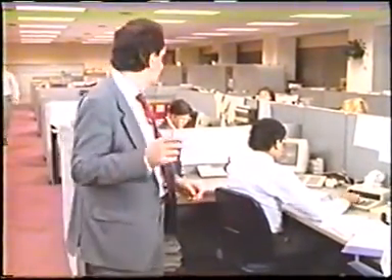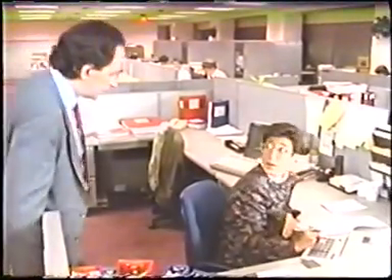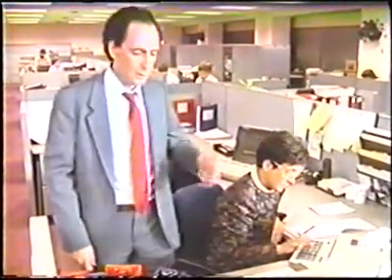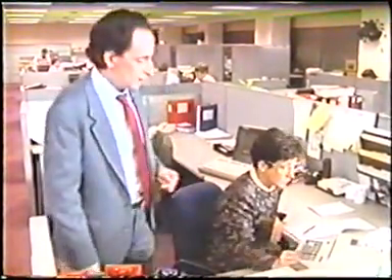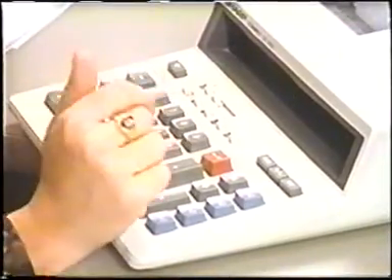Now, when you're evacuating the building, you're not going to be alone, and it's going to take some time. Let's do some calculations. Excuse me, could you help us out for a second? Thanks. Okay, a reasonable pace would be going down about 2 stairs every second, 1,001, 1,002. And we've got 18 stairs per floor, and then add a second for every landing between floors.